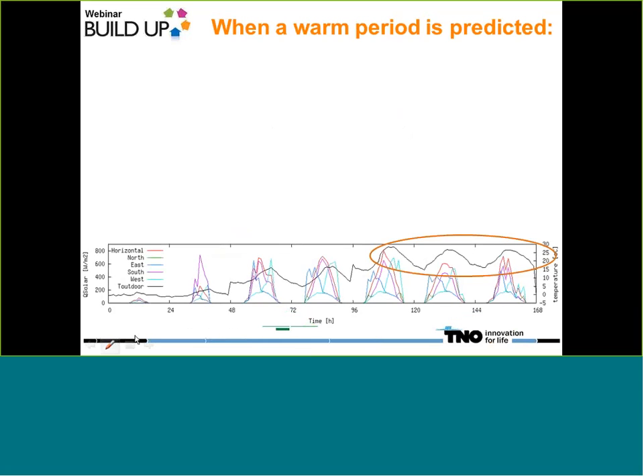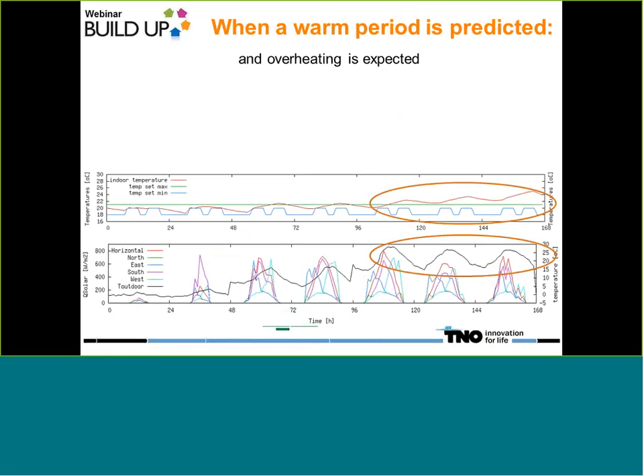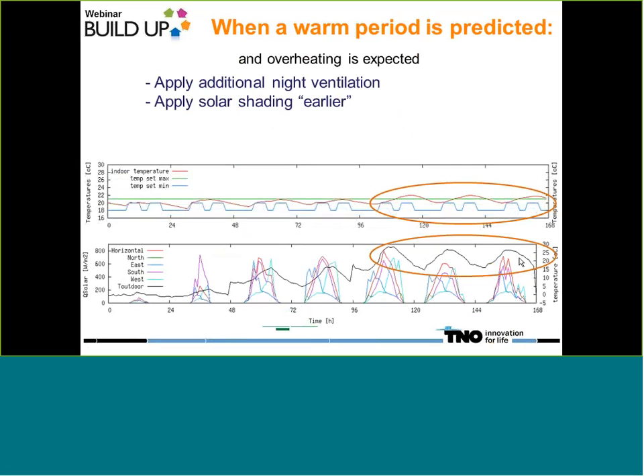To give an example of the control strategy: here you see weather forecast, and hot days are coming up. If you use a conventional controller, you can see that temperature is rising on those hot days. But when we apply additional night ventilation to make it extra cool - because we know a warm period is coming - and apply solar shading earlier, temperatures can stay within comfort levels.